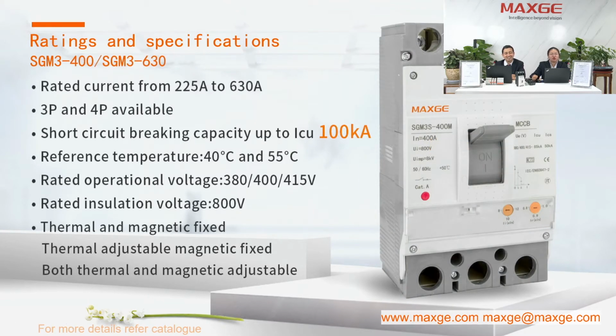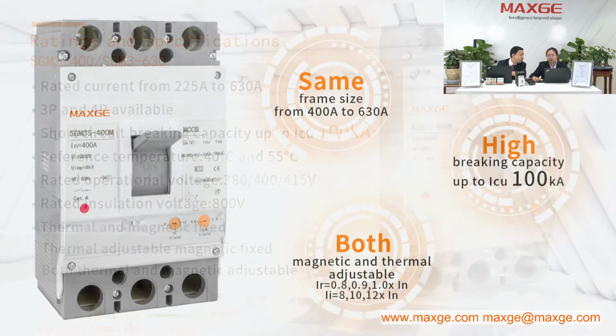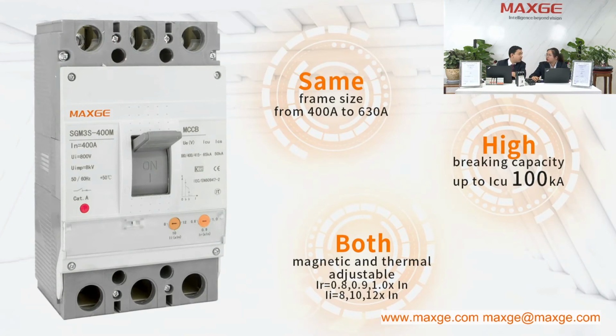And the next one is SGM3-400 and 630. These two ratings are in the same frame, with rated current from 225 to 630 ampere. Here you can see we have high breaking capacities up to ICU 100 kA, and also three choices for the fixed type and the adjustable type. The good thing is we don't have different heights in this frame. We have only one constant height, so the customer doesn't have to choose between different heights. Yes, because you need to consider how to install in the distribution box. Our MCCB of this frame has the same size, and also high breaking capacities.